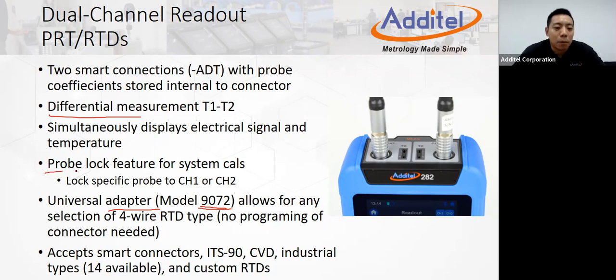Probe lock feature — this is really good for customers who want to use this readout to read both a standard probe and a DUT probe. For example, if a customer has a lot of DUT probes to test in one day or period, they only need one probe as a standard for comparison or calibration, so they can lock channel 1 to the standard probe.